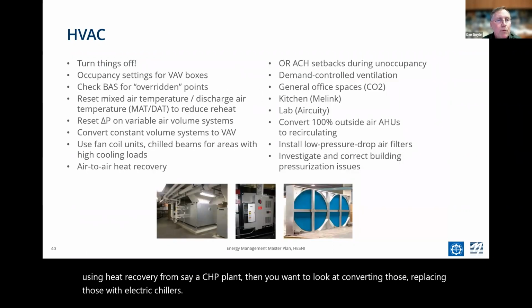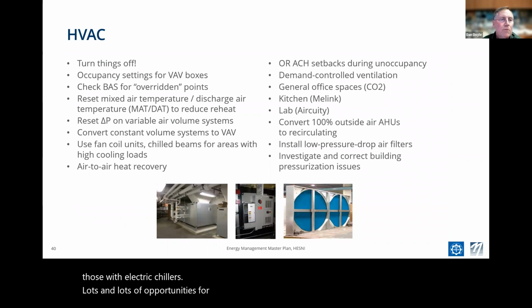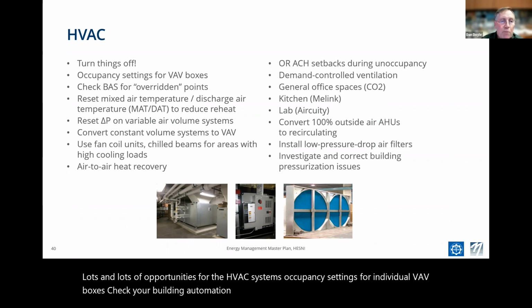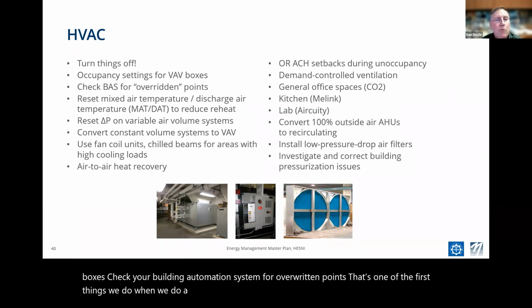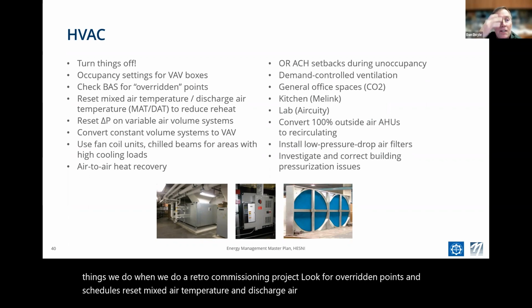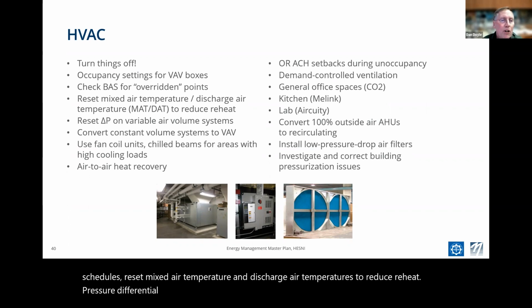Lots and lots of opportunities for the HVAC systems, occupancy settings for individual VAV boxes. Check your building automation system for overridden points. That's one of the first things we do when we do a retro-commissioning project. Look for overridden points and schedules. Reset mixed air temperature and discharge air temperatures to reduce reheat. Pressure differential resets on variable air volume systems.